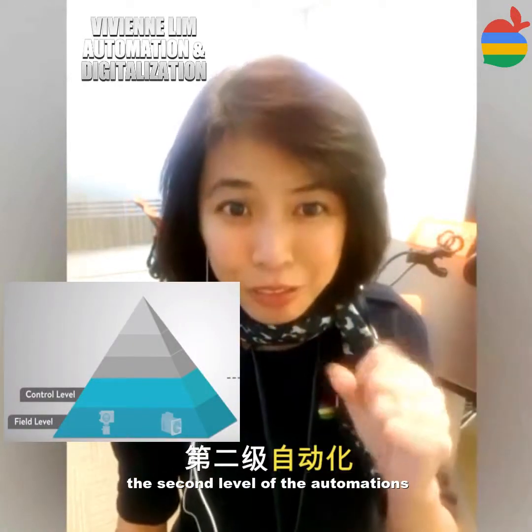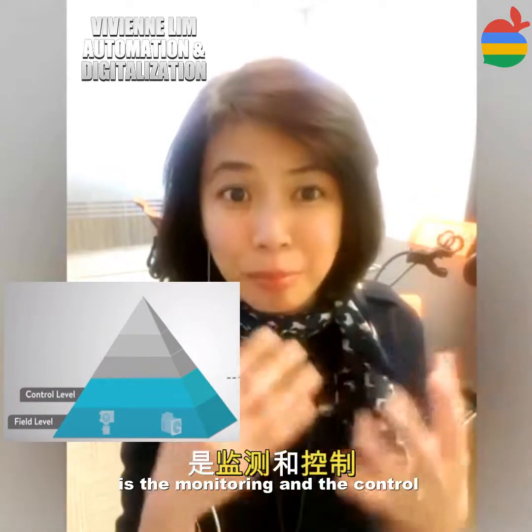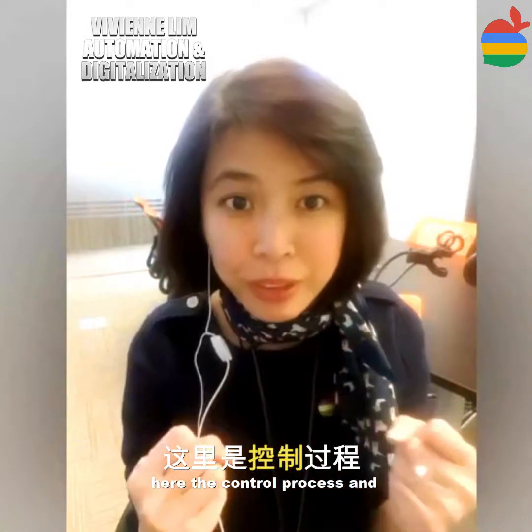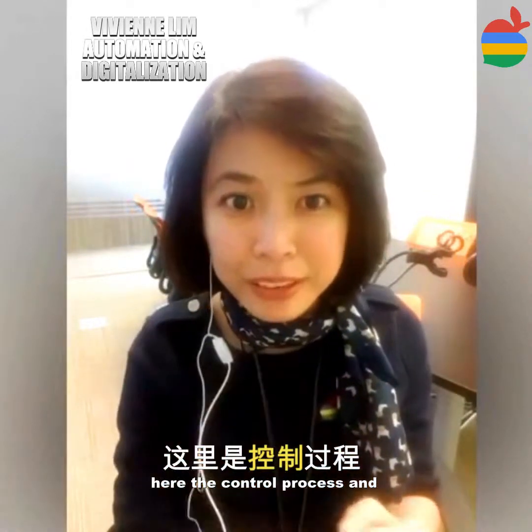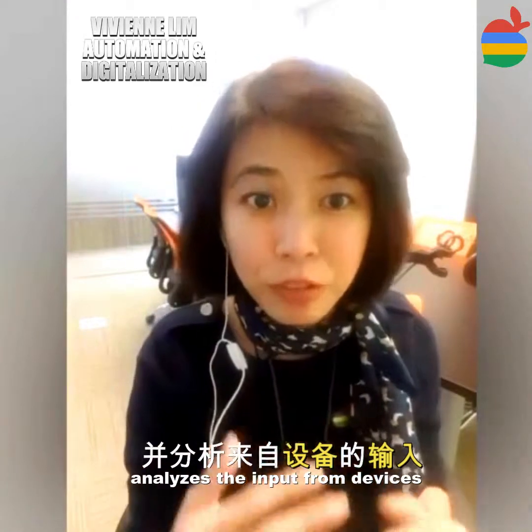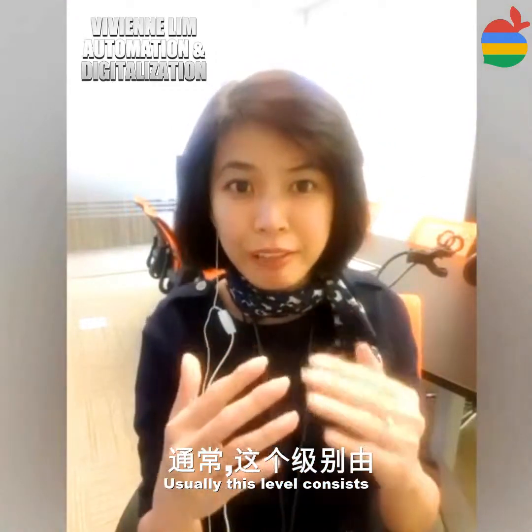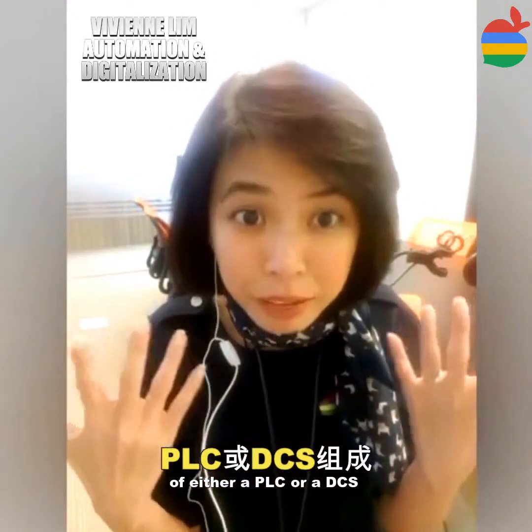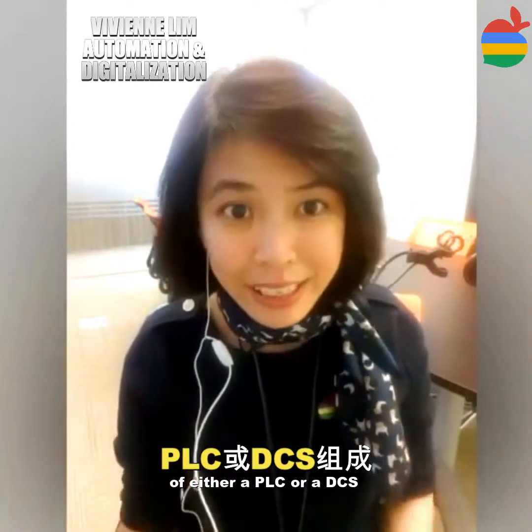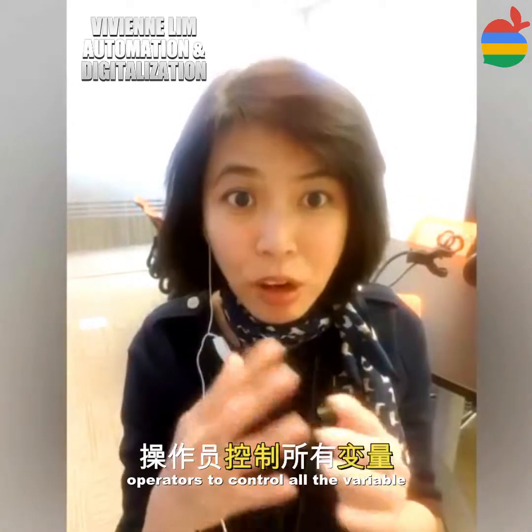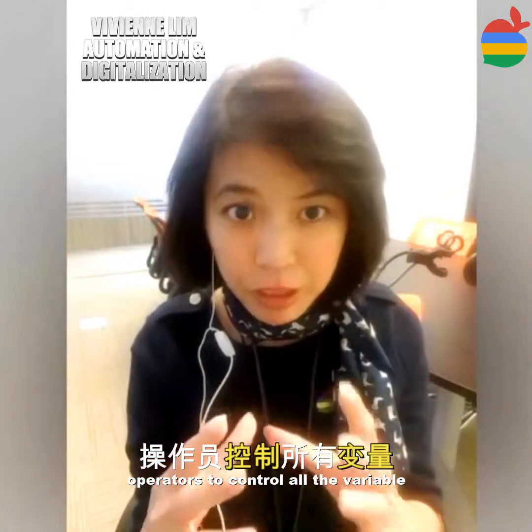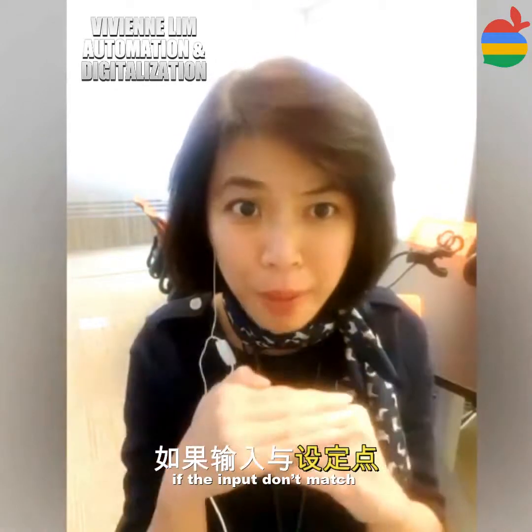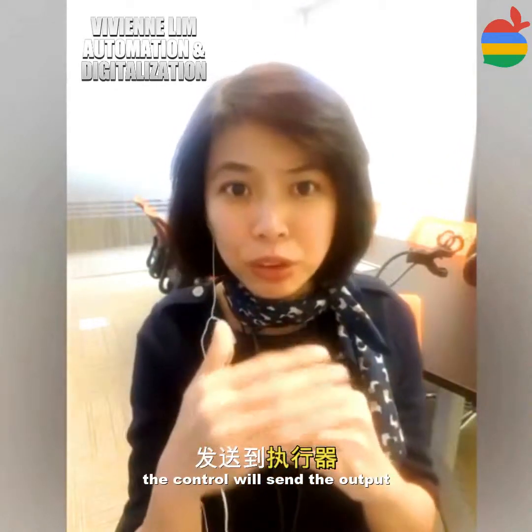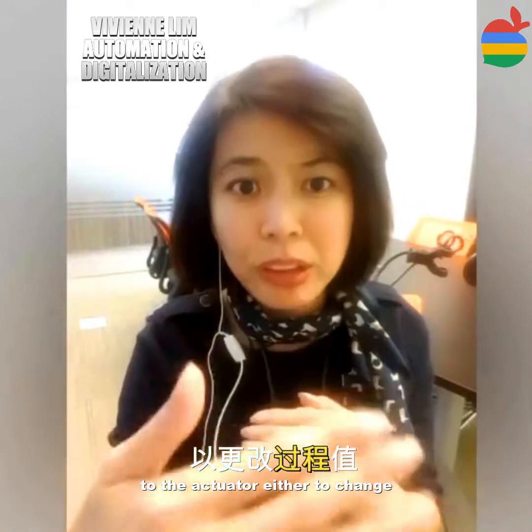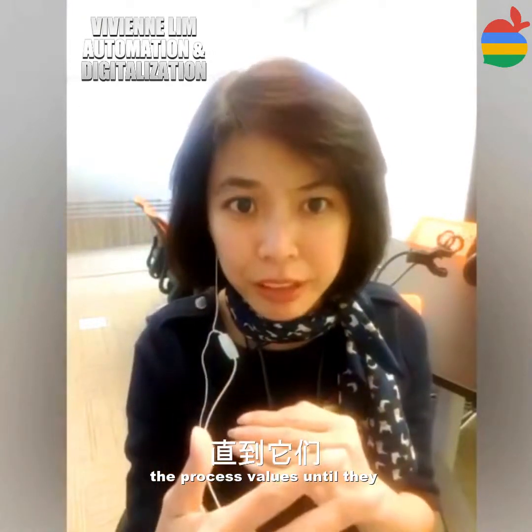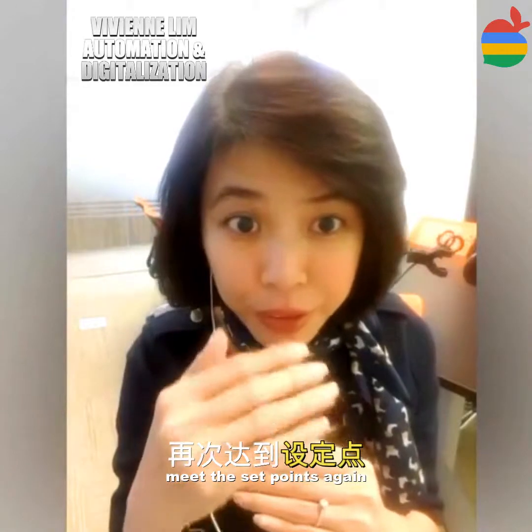The second level of automation is monitoring and control. Here, the controller processes and analyzes the input from devices. Usually this level consists of either a PLC or a DCS. The control layer allows the operator to control all variables. If the input doesn't match the set point, then the controller will send the output to the actuator to change the process value until they meet the set point again.